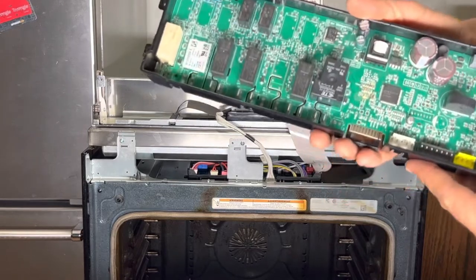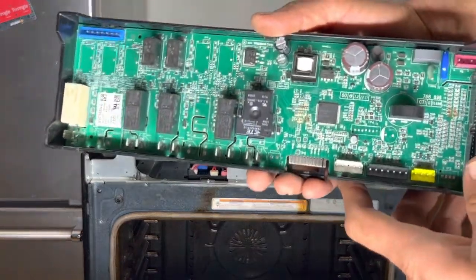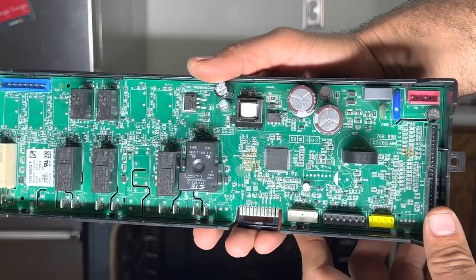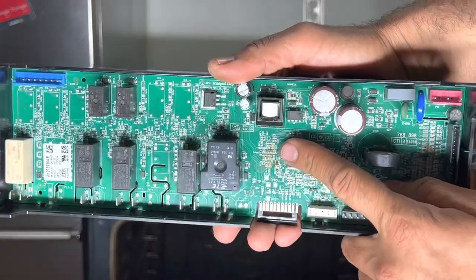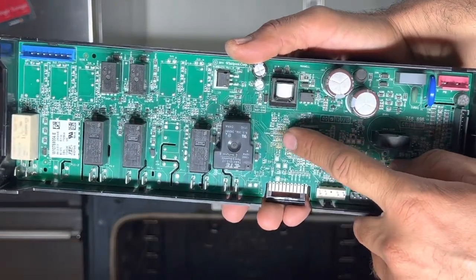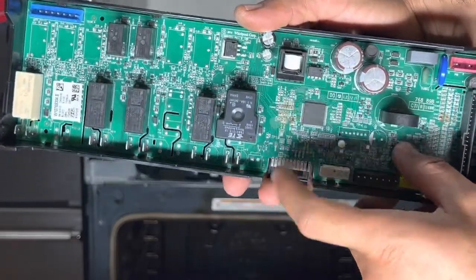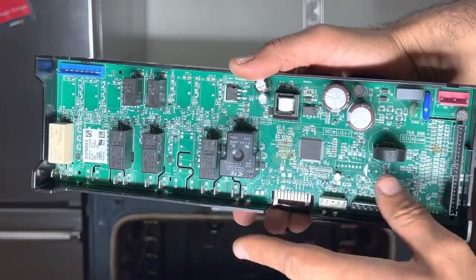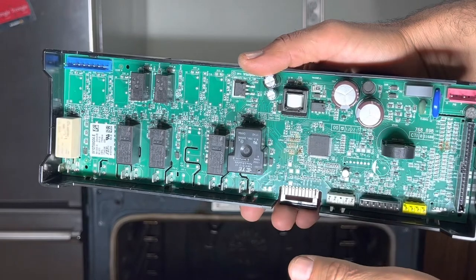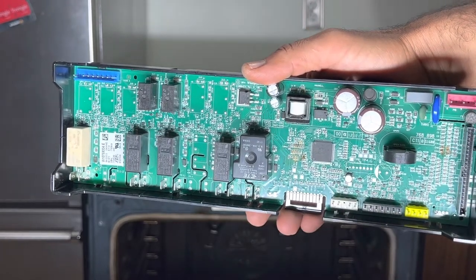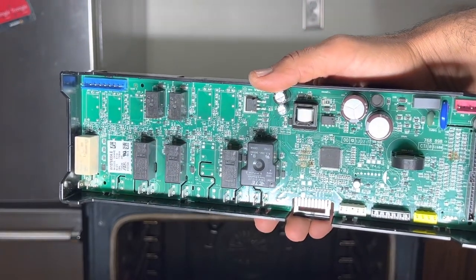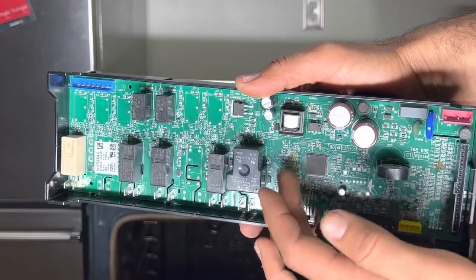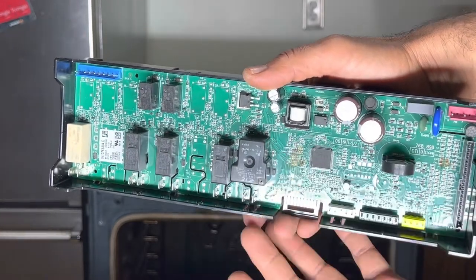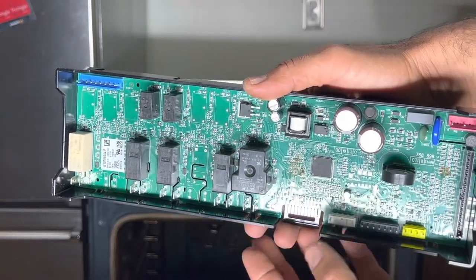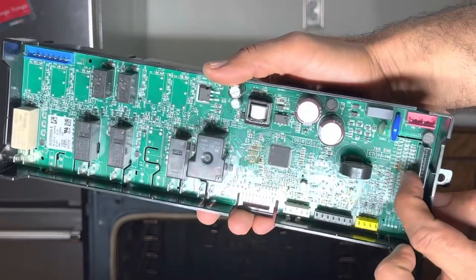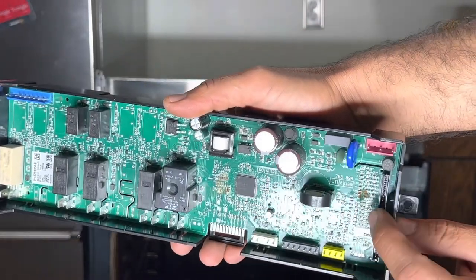And here's the old control board, and I'll show you the spots. I'm sure you can see it, but look at those liquids that fell down here, damaged the small fuses here, and caused that issue. So that's the main problem. If you're not a technician and you just want to see if there's any damage on this unit, you take your control panel off and just look in this area to see if you got some drops in there. That can also tell you that you have a bad board. Look at those drops there. See it.